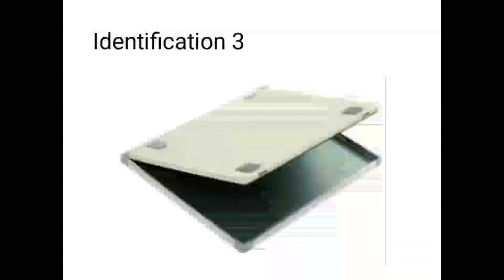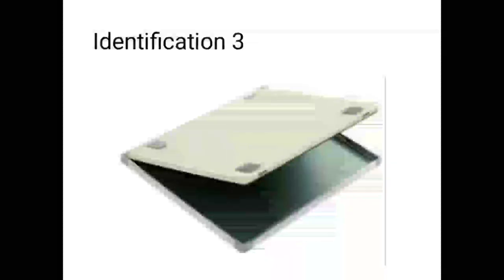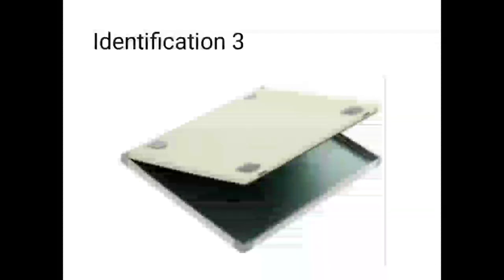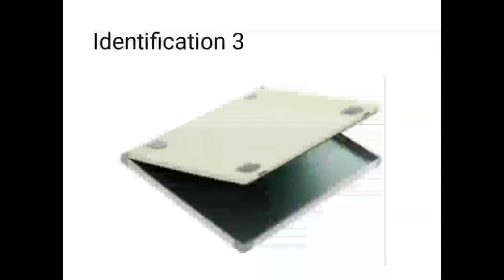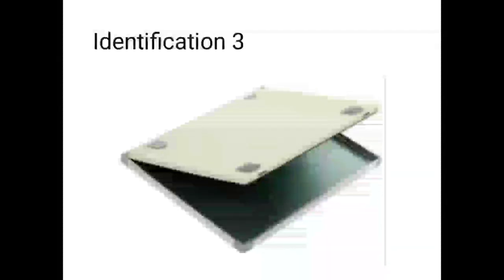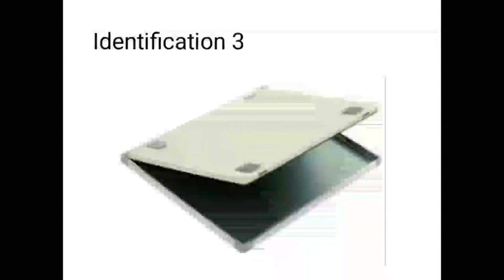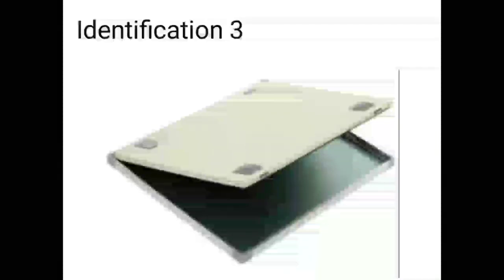What is the size of the cassette? The size of cassettes is measured in centimeters and inches. When it's a mammography cassette, it's always in centimeters. The cassette we see here is a screen film cassette. These are x-ray films and this cassette is a screen film cassette used in conventional radiographic technique.